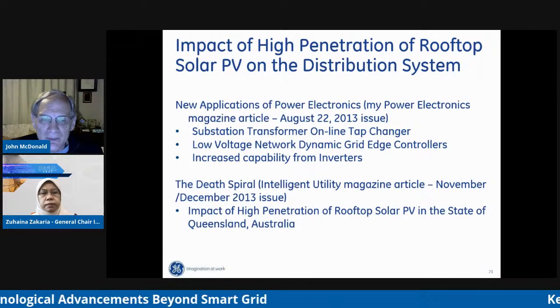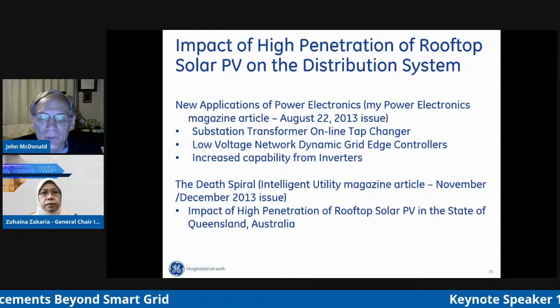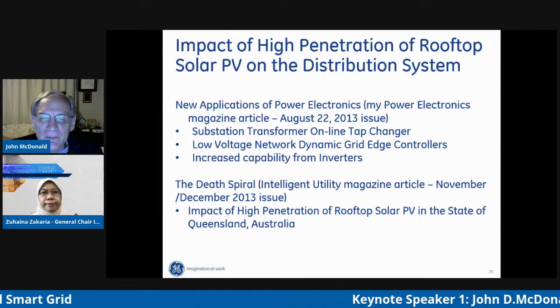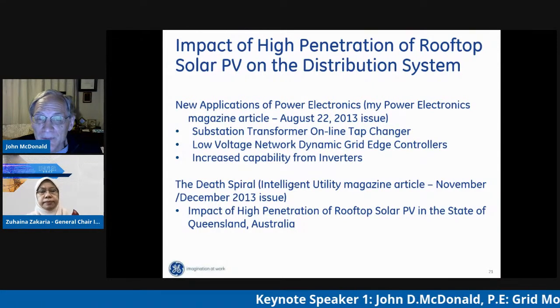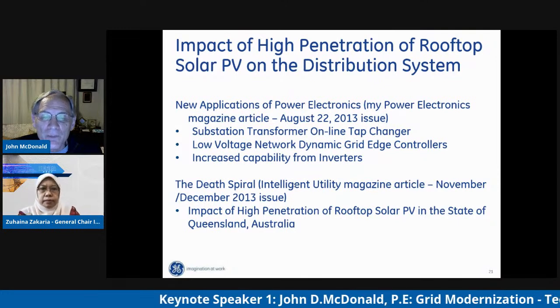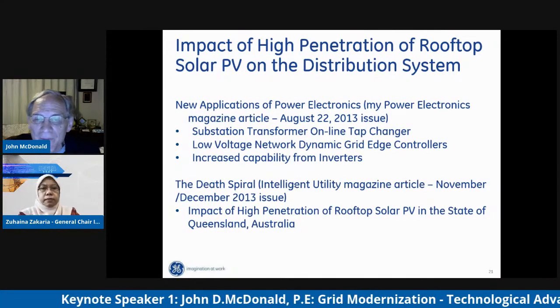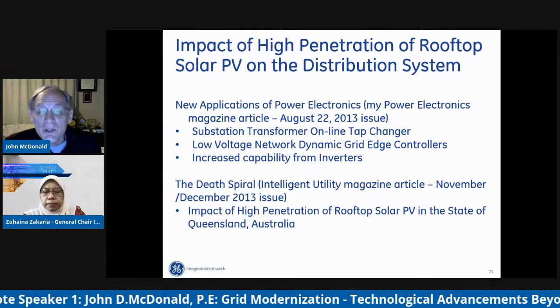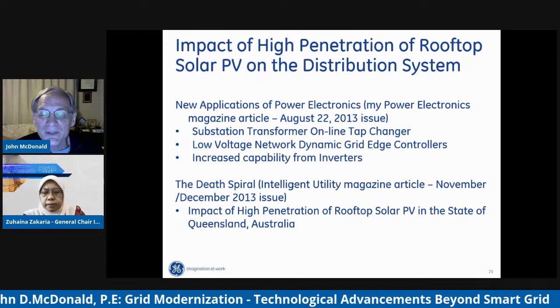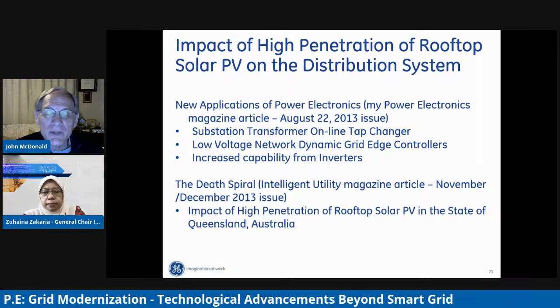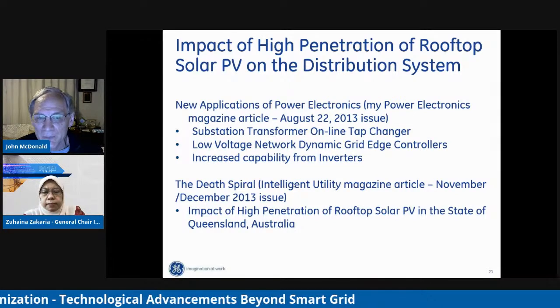With this volatility from the high penetration of renewables, the lifetime of this tap changer in this substation for this feeder went from an expected lifetime of over 35 years to less than 2 years. It was operating 5, 6, 7 times per day. Now it was operating over 120 times per day.